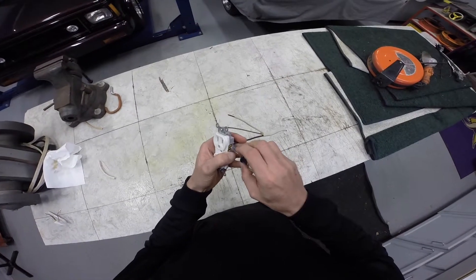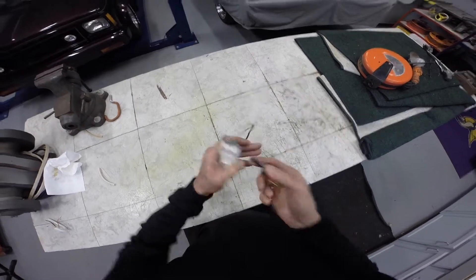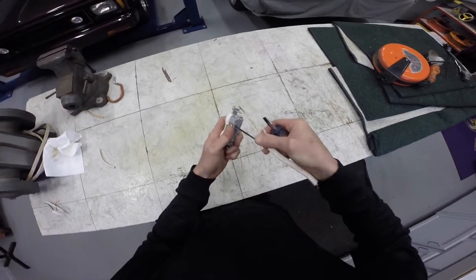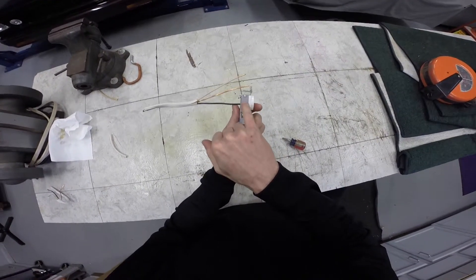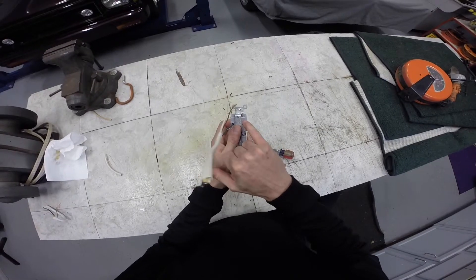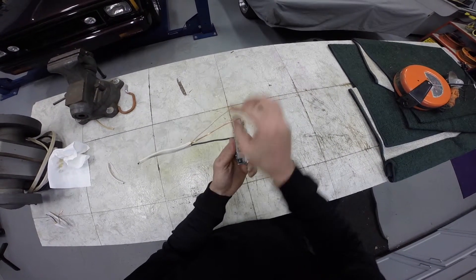The wire should be stripped back three-quarters of an inch, but a lot of these receptacles have a strip gauge. Make sure it's nice and tight. You just got to look around — here it says 'strip gauge,' so this is how much insulation they want you to remove from the wire.